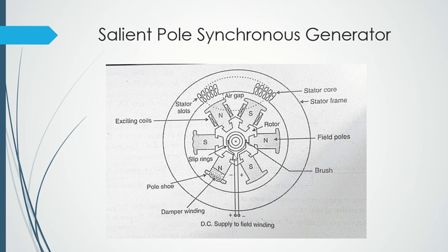The coils will be accommodated in the slots, with flat strips having separators between the turns. And for that, we need slip rings to convey the current. What are the slip rings made of? They are made of copper fitted on micanite. I just told you about micanite; we don't use that so much now, we use synthetic resin, but for the rotor it is used. They are fitted half inside and half outside of your main bearing.